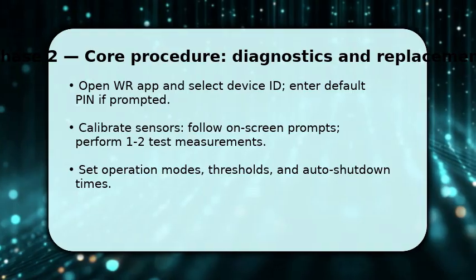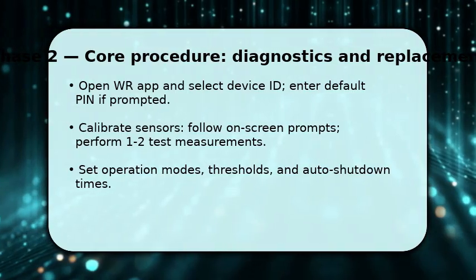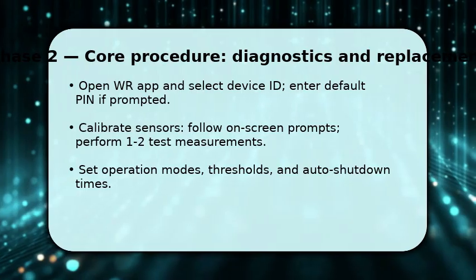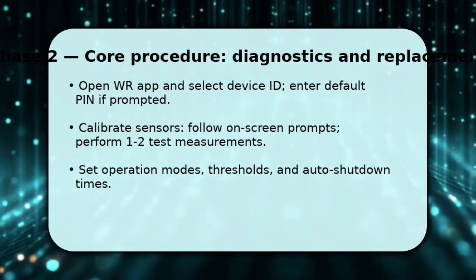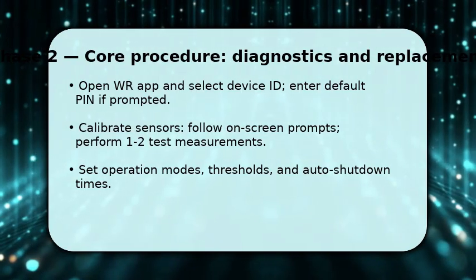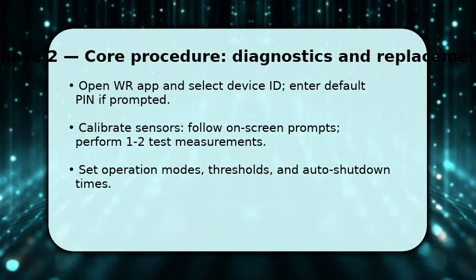Once calibrated, set operation modes, alert thresholds, and auto shutdown timers. This ensures accuracy and battery efficiency. Make sure to save profiles, otherwise you'll repeat calibration later.